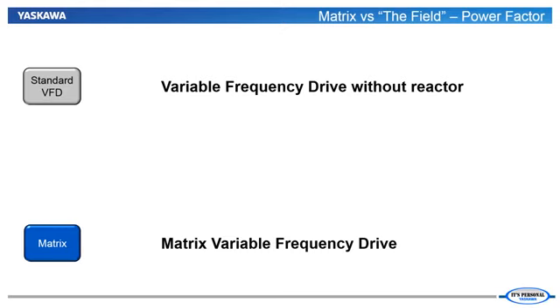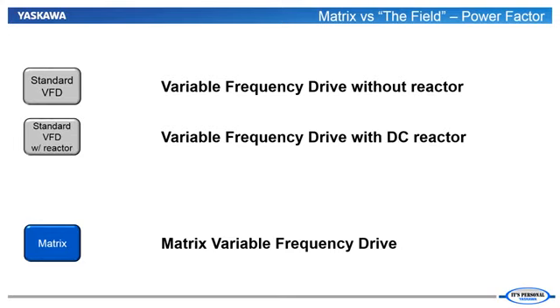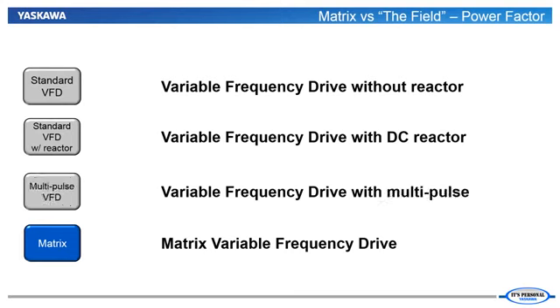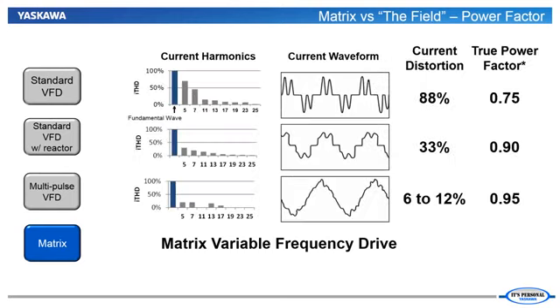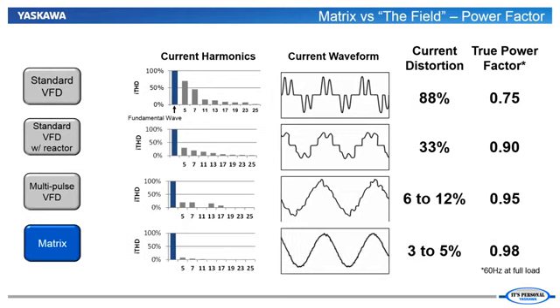Let's compare the matrix to not only the standard VFD, but we will also add performance information for a VFD with an added DC bus reactor and also a VFD with a multi-pulse front end. Only by adding extra equipment, such as DC bus reactors or the special transformer and second rectifier bridge of a multi-pulse VFD, can we begin to eliminate the harmonics and improve the power factor. But even in those cases, we are still not reaching the harmonic mitigation and power factor improvements offered by a standard matrix drive. To minimize the harmonic currents at the input of the drive, you need the matrix drive.